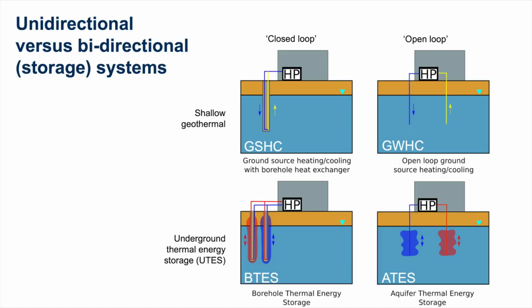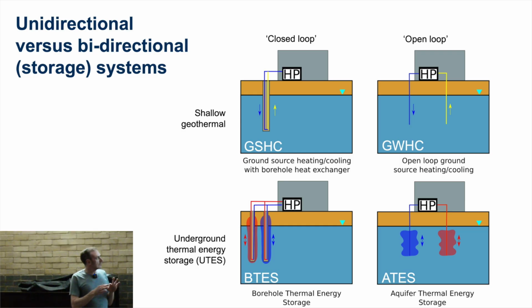Okay, so that's the basic principle. For shallow geothermal, we bring relatively low temperature fluids out of the ground, groundwater out of the ground if it's open loop. And we then take its heat or cool out using a heat pump, and then we pass the waste back into the aquifer. So the best we do is produce water at the ambient aquifer temperature.